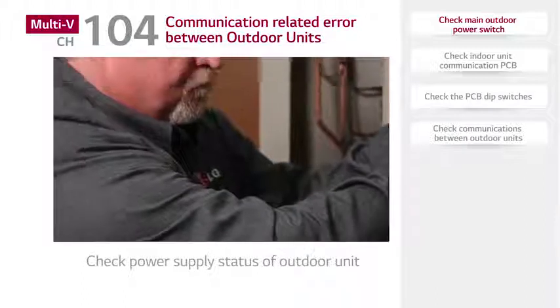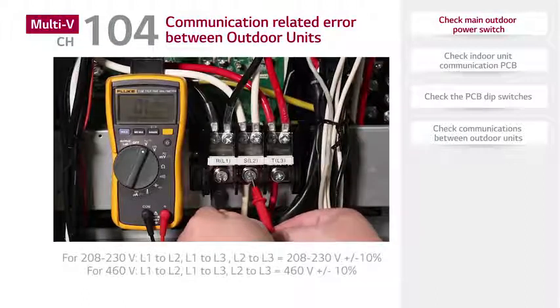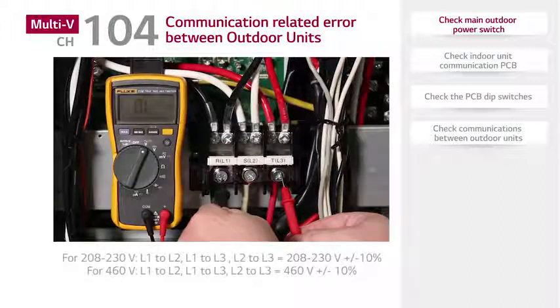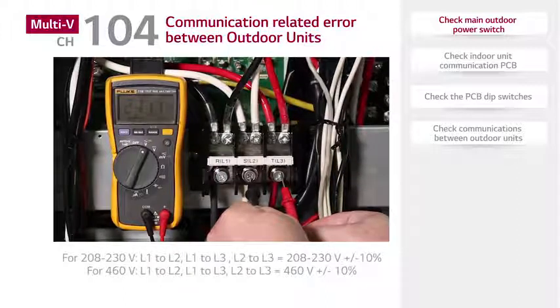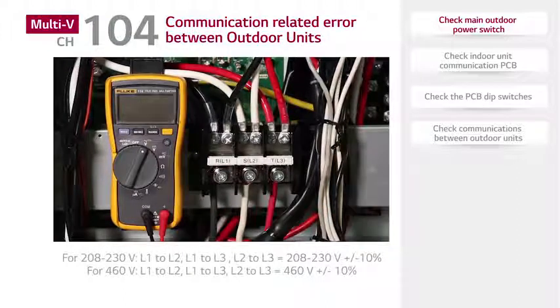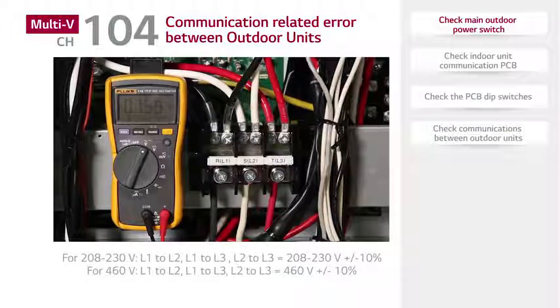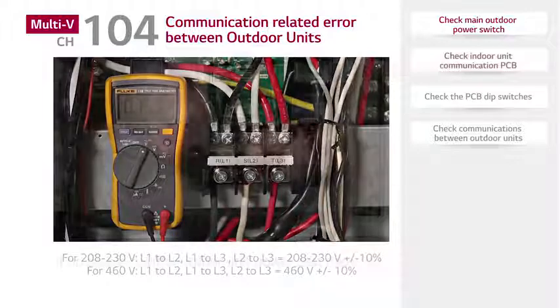The measurements of voltage between phases are as follows. For 208 to 230 volt units, L1 to L2, L1 to L3, and L2 to L3 readings should be 208 to 230 volts plus or minus 10%. For 460 volt equipment, L1 to L2, L1 to L3, and L2 to L3 readings should be 460 volts plus or minus 10%.